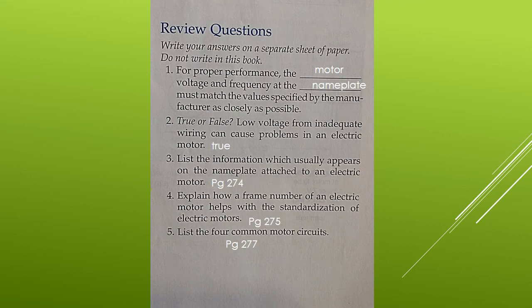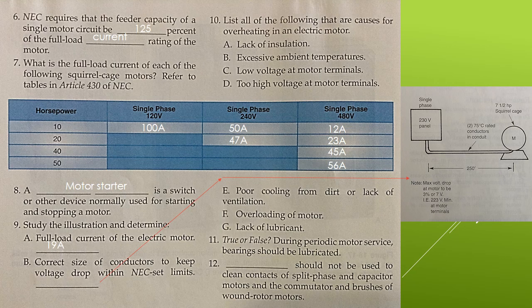The tables that you must refer to are 430.248 and 430.249 of the 2011 NEC. And you would see that for a single phase 10 horsepower motor, you would need a 100 amp. For a single phase 240 volt, 10 horsepower motor, it would have a 50 amp full load current.